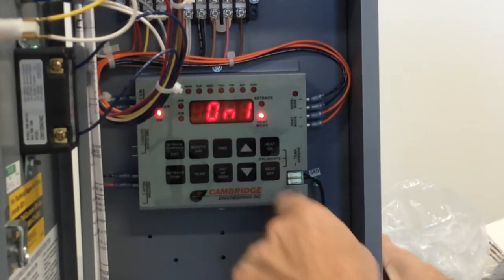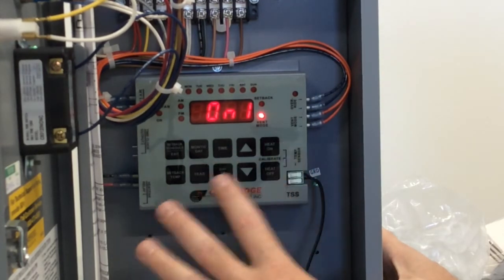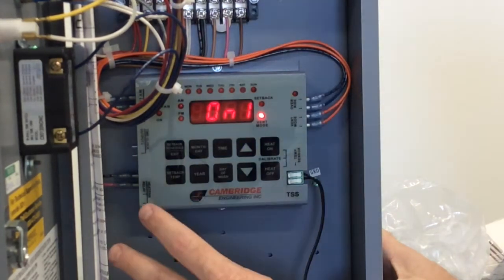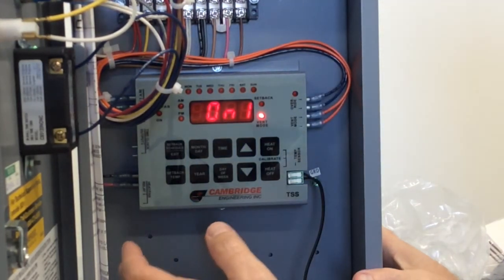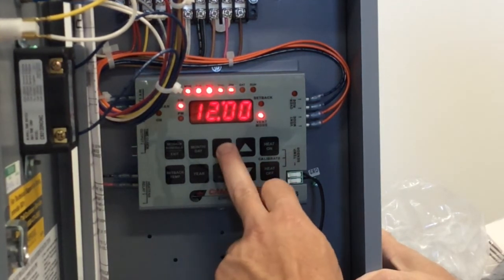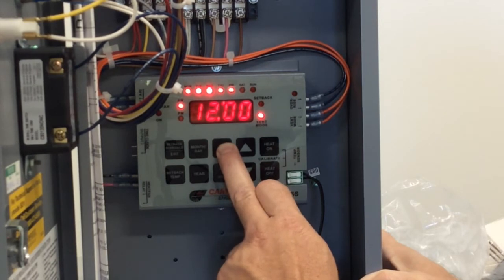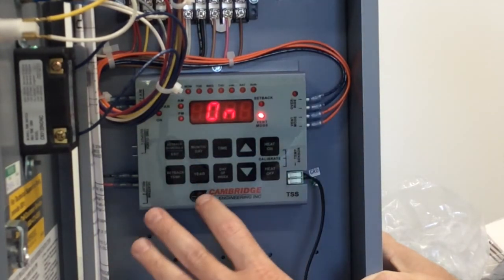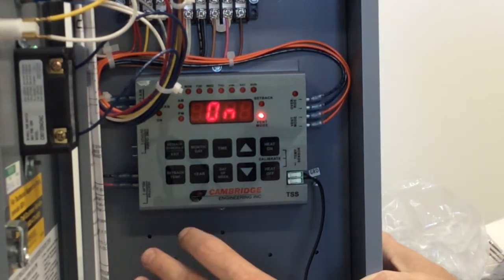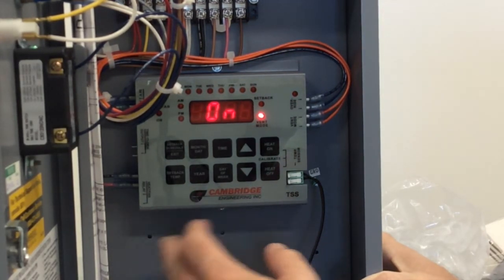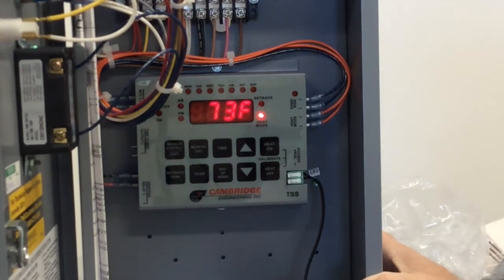Now as you can see, the Monday through Friday is lit up, so we're only setting Monday through Friday. You can also see the vent mode light is on. Whenever that vent mode light is on, the blower should be running. And then now we hit the up arrow again. It's going to say on one. Now there's also presets in here for up to 14 separate programs. You can basically program two per day if needed. But typically, most folks are only going to run one shift, maybe two. So a lot of times you can utilize that Monday through Friday and set those preset times in. And remember, what you're doing is you're setting your occupied mode. Typically, unless you're in the ventilation mode, we're basically going to program our unoccupied mode and bring in the cool air for the night when nobody's there.